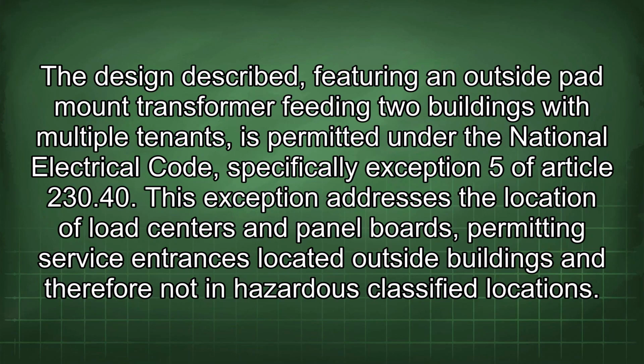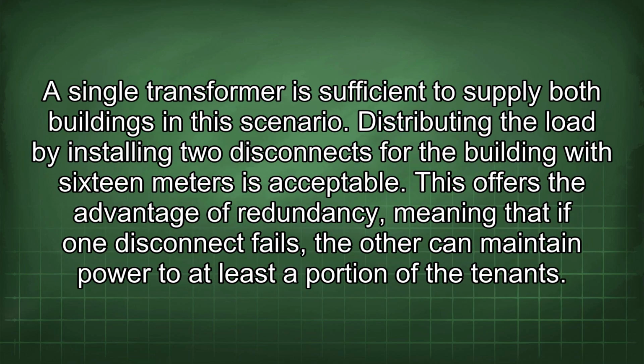The design described, featuring an outside pad-mount transformer feeding two buildings with multiple tenants, is permitted under the National Electrical Code, specifically Exception 5 of Article 230.40. This exception addresses the location of load centers and panel boards, permitting service entrances located outside buildings and therefore not in hazardous classified locations. A single transformer is sufficient to supply both buildings in this scenario.